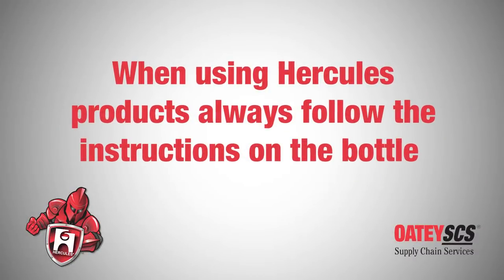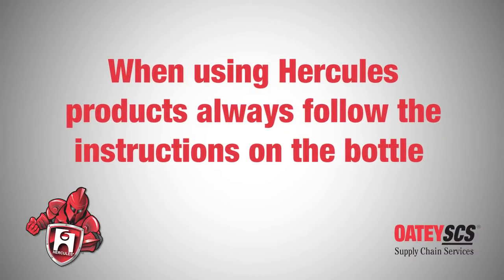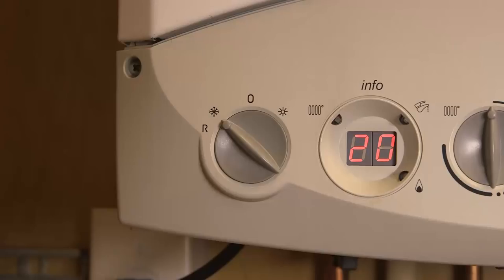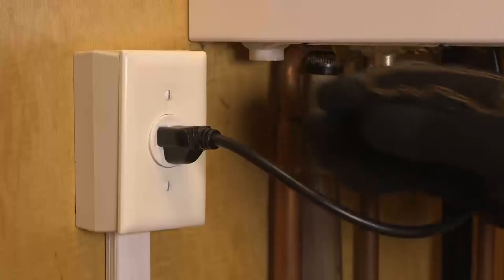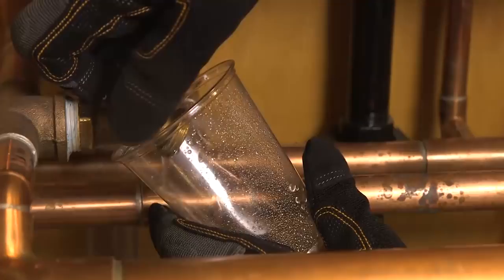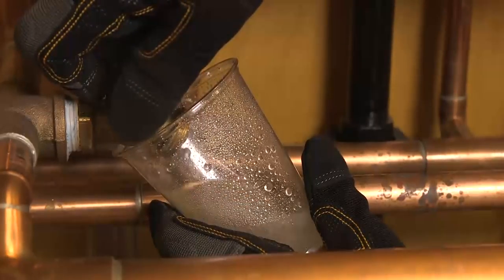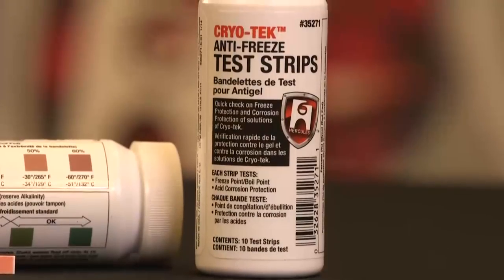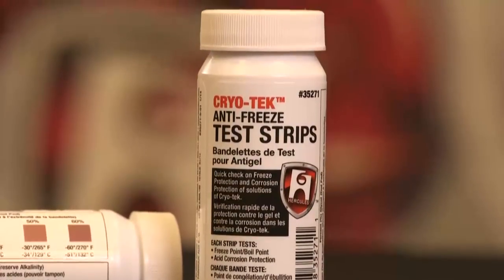Be sure to follow the instructions on the back of the bottle. First, turn off the gas and auto feeder if there is one, and disconnect the electrical supply. Open the drain valve, remove a small amount of liquid, and close the valve. Check corrosion inhibitor or propylene glycol levels with Cryo-tek test strips.